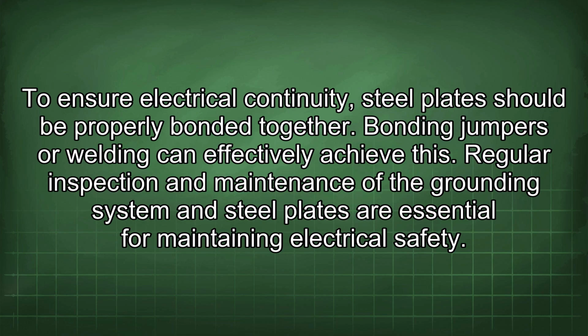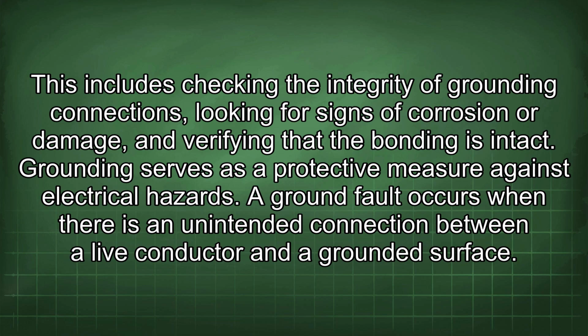Regular inspection and maintenance of the grounding system and steel plates are essential for maintaining electrical safety. This includes checking the integrity of grounding connections, looking for signs of corrosion or damage, and verifying that the bonding is intact. Grounding serves as a protective measure against electrical hazards.